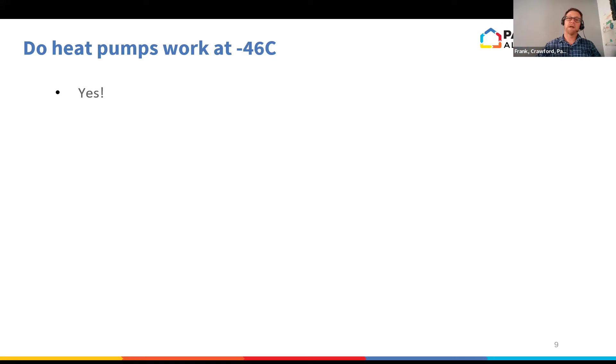Another question that comes up all the time is whether heat pumps work in our cold climate. The short answer is yes. At minus 46, air source heat pumps won't produce much heat from the air, and below about minus 25 to minus 30 with some equipment, they'll switch to a secondary heating system as the compressor turns off. That secondary system could be electric or fossil fuel. Historically there are only about 5 days a year in Edmonton and about 4 in Calgary below minus 25, so a secondary heating system is needed with air source heat pumps, but it won't be used very often. The rest of the time, air source heat pumps work fine.